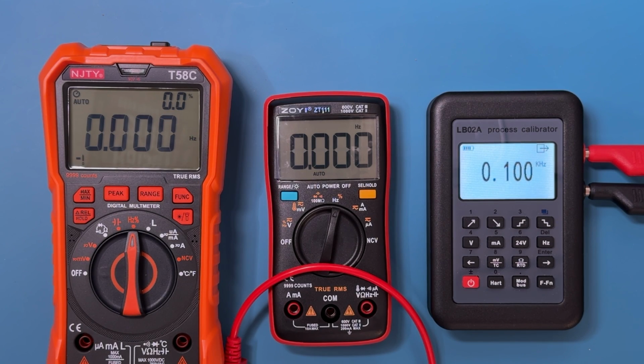There are a variety of devices that put out a signal with varying frequency. Multimeters have expanded beyond the basics of voltage, resistance, and current to include the ability to measure a wide variety of electrical properties. One of the trickier ones appears to be frequency and duty cycle. This was not a capability that I paid much attention to early on. However, since getting my LB02A process calibrator, I have been testing it. Many multimeters that claim to support frequency measurement are unable to detect and measure the square wave signal produced by the calibrator. Square wave signals are often used for communication between devices in industrial control systems, and these meters are usually capable of measuring the sinusoidal signal of AC power systems.